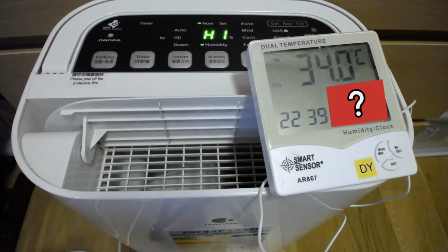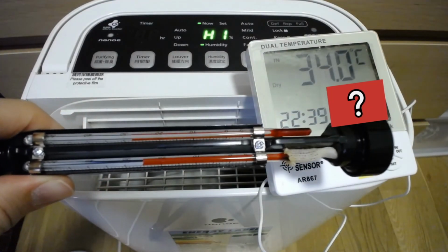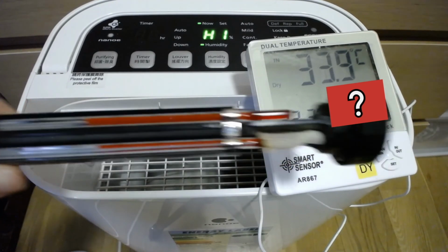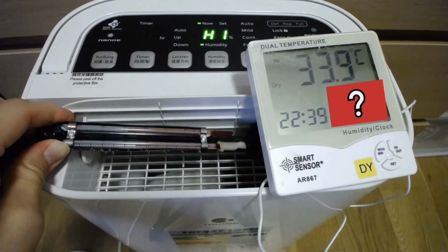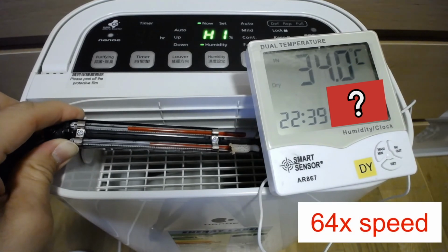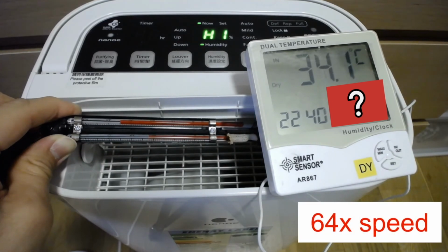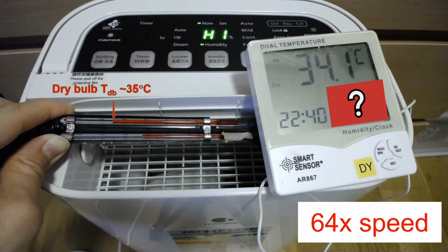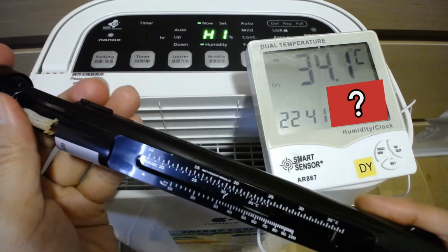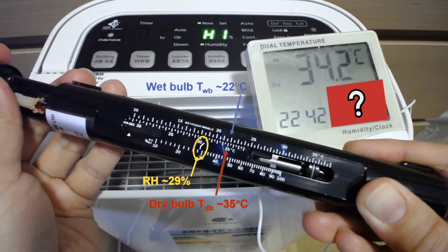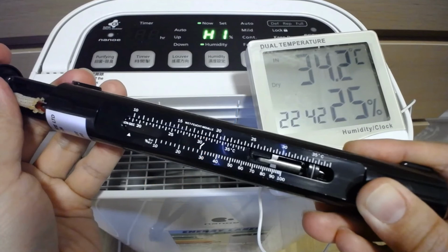We can also check out the condition of the air coming out from a dehumidifier here. As the dehumidifier already has air blowing from it, there is no need to sling the hygrometer. We can just put the hygrometer at the outlet and wait. We can see the temperature difference gradually increases, and the resulting dry bulb temperature is about 35 degrees Celsius, and the wet bulb temperature is about 22 degrees Celsius. This corresponds to a relative humidity of about 29%. The digital hygrometer gives a relative humidity of 25%, which is quite close to that measured by the Sling hygrometer.